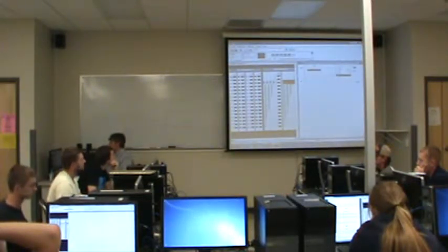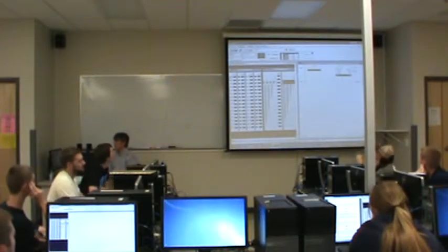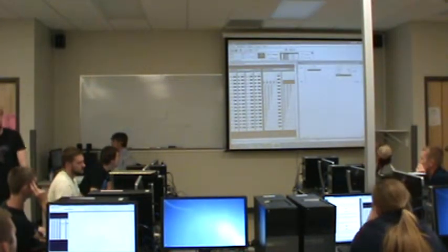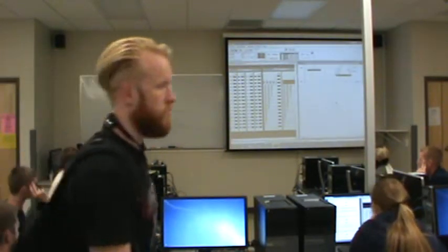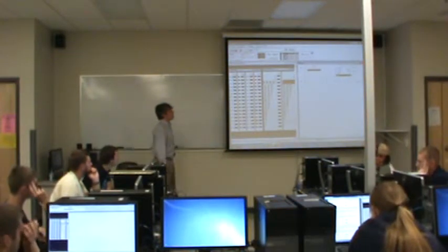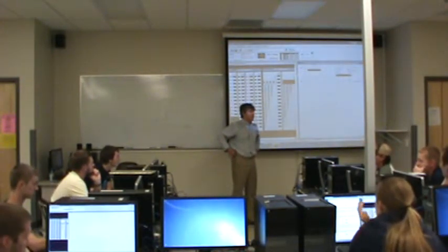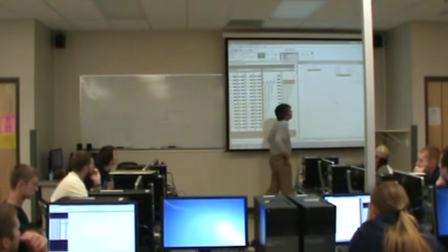Now I'm going to change this to a momentary switch. And the way I did that, if you're wondering, is I right-clicked on it. You can right-click through it and cycle through the different types of switches. So let's download that and run it. Now the counter is already at 1. What that tells you is that these counters are retentive. They don't just lose their count when the PLC quits, when the program quits. So in memory somewhere there's a 1 that has been counted.